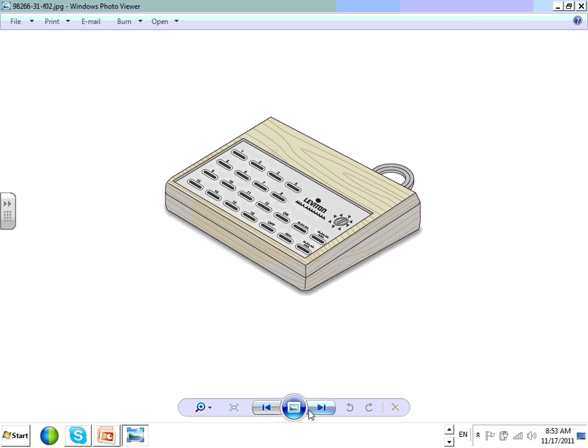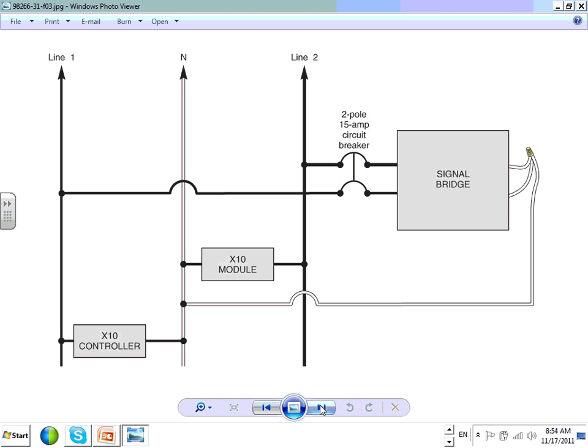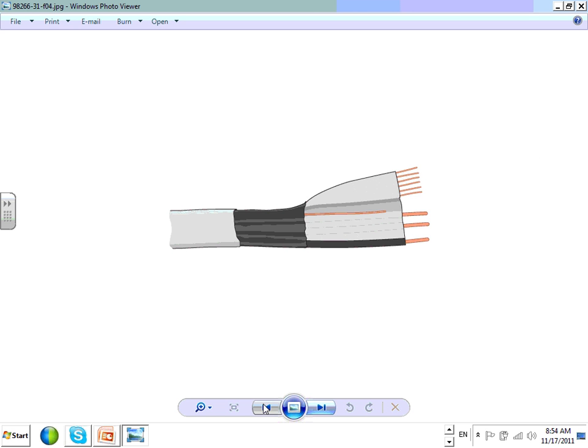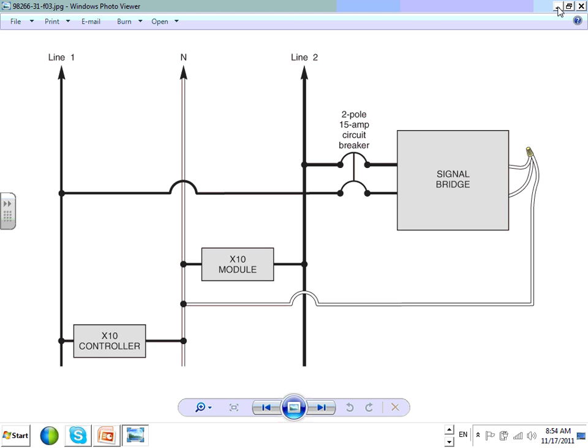One of the major problems with that older stuff is what's called ears only. It would hear, but it would not reply. So if you say turn off, it doesn't confirm. There's no acknowledgement. So you can get out of sync, and a lot of them were simple toggles. If it heard a signal, it changed position. Well, if you don't know where you were to begin with, you don't know whether it's on or off. It creates total havoc, and that's what we found over a few months. So that's not the most adaptable, but it's cheaper equipment. So that's basically your technology.